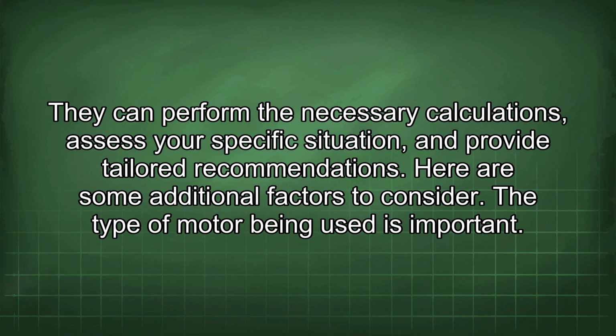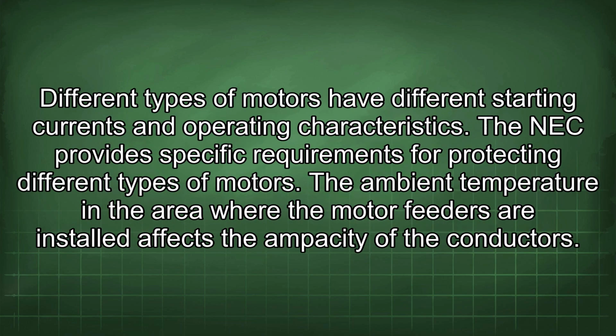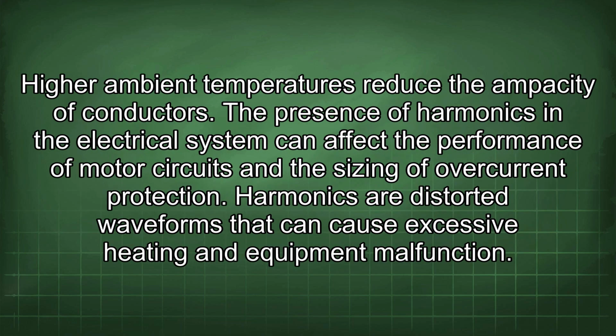The type of motor being used is important. Different types of motors have different starting currents and operating characteristics. The NEC provides specific requirements for protecting different types of motors. The ambient temperature in the area where the motor feeders are installed affects the ampacity of the conductors. Higher ambient temperatures reduce the ampacity of conductors.